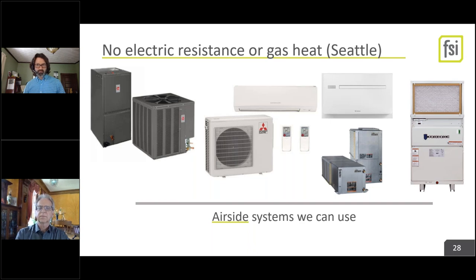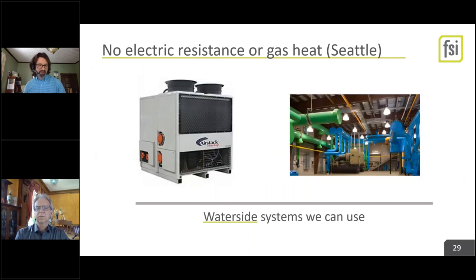And it's not new. You know, we've been doing VRF in a lot of buildings just on a cost basis prior to this code change. So this is not a thing to freak out about. And then next slide, on bigger buildings, it also opens up a bunch of options on the hydronic side. The left side is a heat pump chiller. Like I said, it looks a lot like a chiller, and that's just a two pipe sticking out. Or centrifugal chiller plants, you can do some really neat heat recovery things when you've got a four pipe chiller plant only on very large buildings.